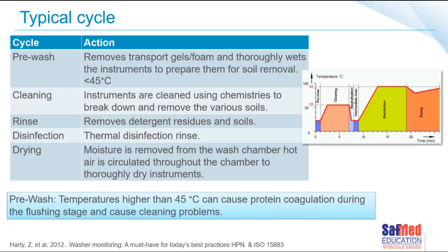The cleaning or wash phase is where instruments are cleaned using chemistries to break down and remove the various soils. In the rinse phase, detergent residues and soils are removed. The disinfection phase is a thermal rinse — a rinse at a specified temperature for a specified time to thermally disinfect the instruments, making them safer to handle. After that, the drying phase removes moisture from the washer chamber — hot air is circulated through the chamber to thoroughly dry the instruments. It is really very difficult to replicate this process in manual cleaning.